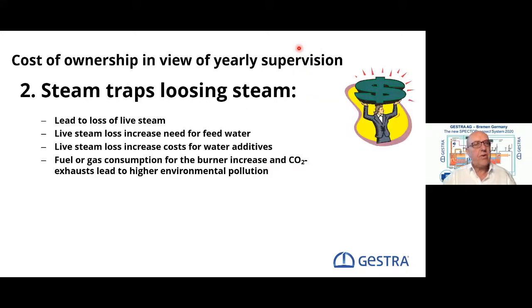If we look at the cost of ownership in view of the yearly supervision, we have now to consider the loss of live steam. Live steam loss increases the need for feed water, live steam loss increases the cost of water additives, and the fuel or gas consumption for the burner increases, and CO2 exhaust will lead to higher environmental pollution. And this is what we have to consider, what happens there.